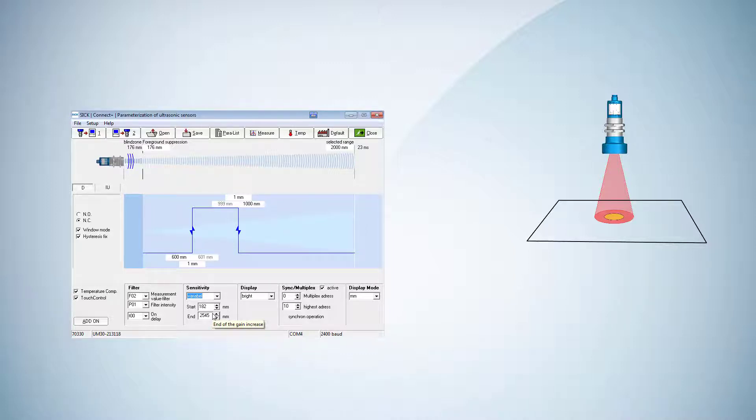We can adjust the start and end value of the linear increase of echo amplification. In our application, we want to set the sound cone as narrow as possible to look through the hole. We set the end value to the highest possible value in order to have the lowest increase in echo amplification and thus in sensitivity and sound cone size. Then we write the data into the sensor.